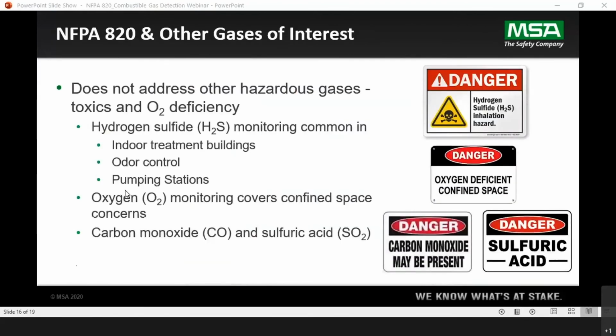NFPA 820 and other gases, I just want to mention that it does not specifically address toxics like H2S and oxygen deficiency. H2S is a concern as a toxic, and many users will design for H2S detection in indoor treatment buildings, especially in odor control operations and the pumping stations themselves. There have been concerns in small spaces without ventilation. If you open up or work on a pump, you could have H2S gas present.